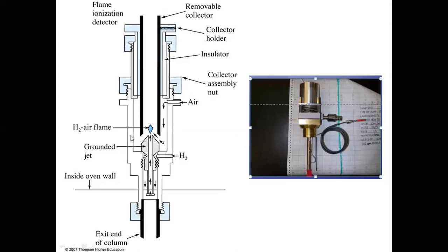So this is the schematic representation of the flame ionization detector, which has a provision for the passage of hydrogen gas, a mixture of hydrogen gas and air, and the flame is ignited by allowing the mixture of hydrogen and air. This flame is given the provision to get aspirated with the effluent from the chromatographic column, where the combustion is going to take place. After the combustion, the collector electrode will attract the positively charged species if the collector electrode is negatively charged. If the collector electrode is positively charged, anions are going to be attracted, and vice versa.